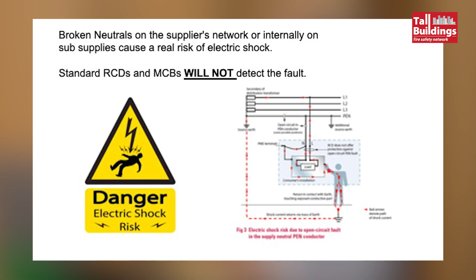It's pretty spooky. So this only came out about a week ago, and this is the IET now making everyone aware that there's a massive problem in the UK. Read it for yourselves, I won't go through it all, but the big part is at the bottom. I'll try and read it on my screen. Should be remembered, the NCD can cause hazardous touch voltages to appear on all extraneous conductive parts and exposed conductive parts of the installation, as well as fire, explosion and damage to electrical equipment. Therefore, the IET and our industrial partners strongly advise anyone who suspects NCD to present a report. We've seen, and we've got reports here, there's over 6,500 incidents a year that are reported. That's only reported. There's many, many more that won't be.